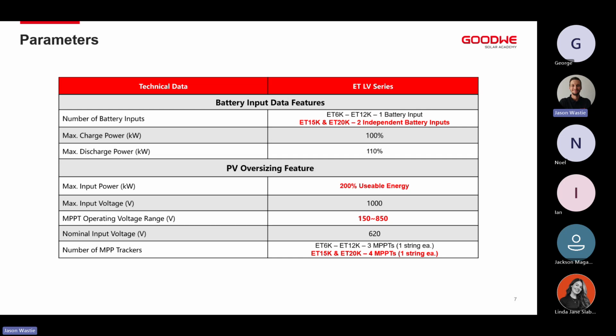Our nominal is 620. So at 150 volts, probably not going to be running many loads or any loads at that point of view. However, we get 10 or 15 minutes extra in the morning of PV power, 5 minutes in the morning, 10 minutes in the afternoon, whatever it is. But it's that additional PV power that we get to generate. Like I said, it's probably not going to run your loads, but it will charge your batteries during those times. So it allows your batteries to float for a bit longer, start charging a bit earlier.